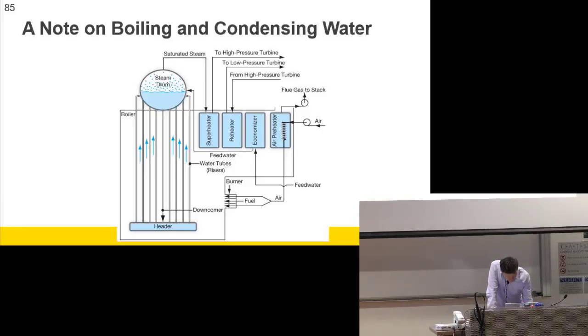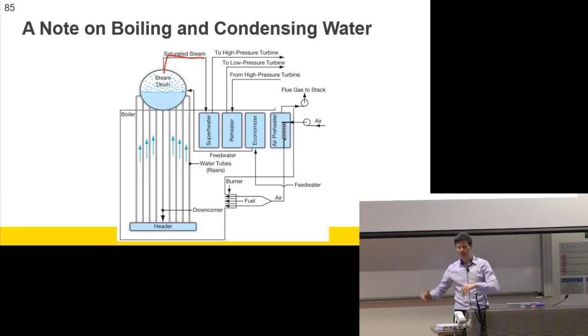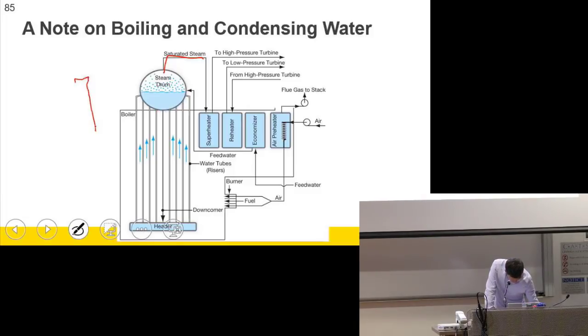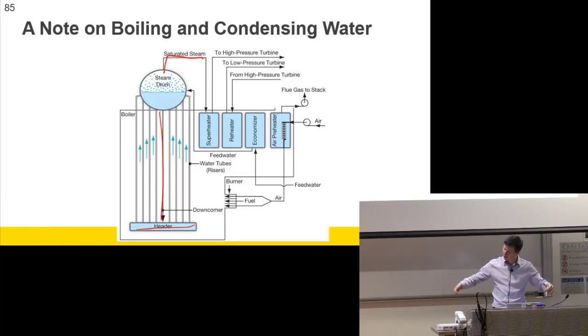So here's a steam drum, and there's some liquid in it and some steam in it. So you know that the output from that is saturated steam. So that's kind of nice. It's having liquid come down a downcomer, down to a header. A header is a pipe with lots of offtakes. Okay? So it's coming down probably a big pipe down the middle, and then being distributed into a header, and then all of the offtakes are coming back up.